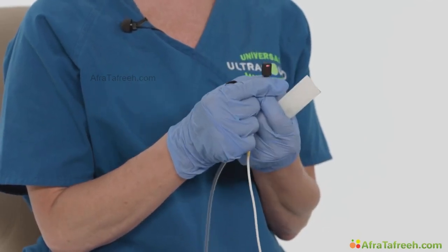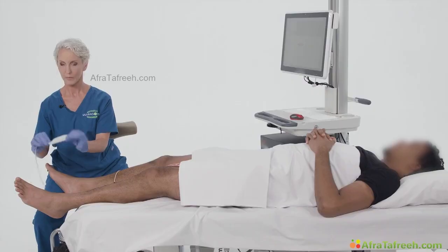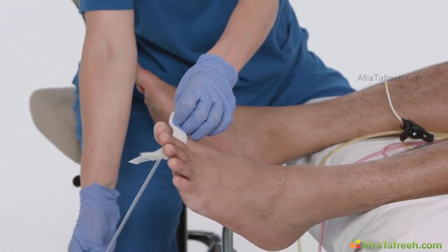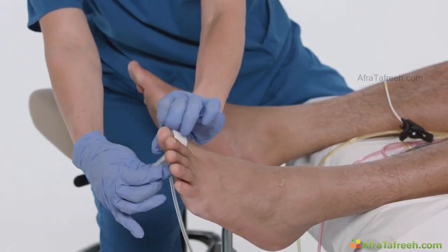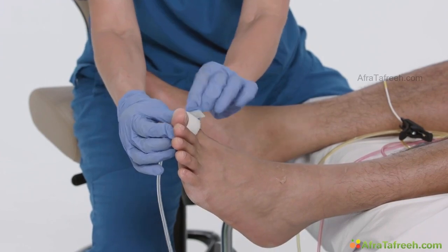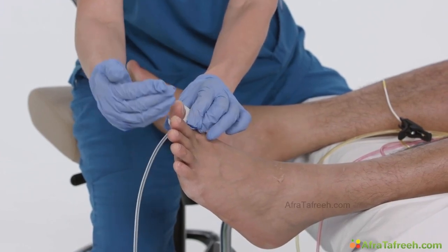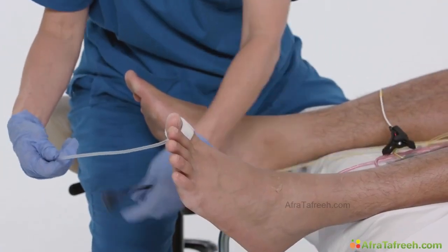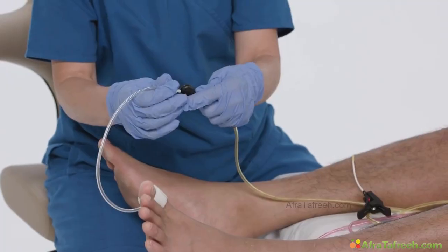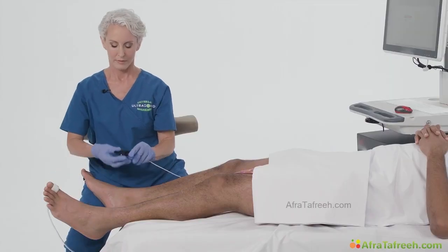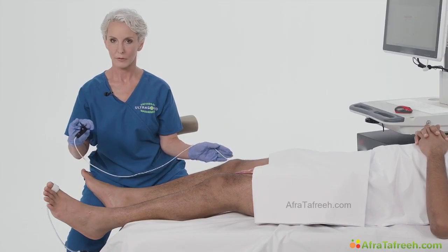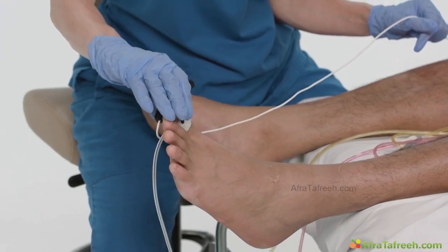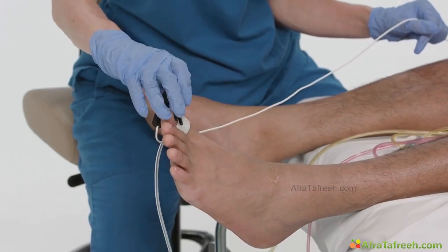This photosensor senses cutaneous flow. I'll wrap the digit cuff around the great toe with the hose pointed down towards the ground. This will allow me to fully wrap the cuff around the toe without having to reach in between the toes. Then I connect the air hose, and then I will apply the photosensing technology to the toe. Now, if you don't want to use a clip, like I'm showing you here, you can simply tape it to the toe.